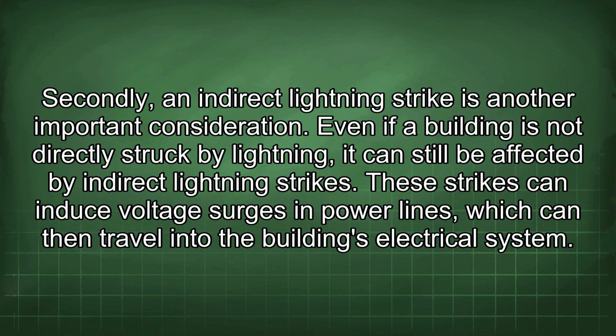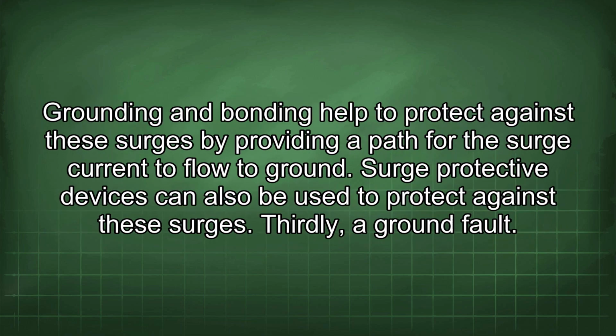Secondly, an indirect lightning strike is another important consideration. Even if a building is not directly struck by lightning, it can still be affected by indirect lightning strikes. These strikes can induce voltage surges in power lines, which can then travel into the building's electrical system. Grounding and bonding help to protect against these surges by providing a path for the surge current to flow to ground. Surge protective devices can also be used to protect against these surges. Thirdly, a ground fault.